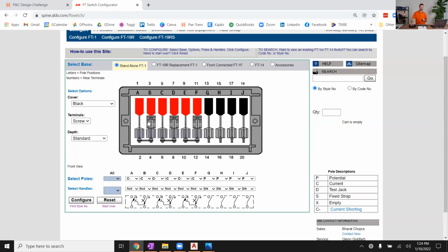If you open the A, or you open the B, or you open A and B, it actually short circuits the field side. I should specify that up here, the odd number terminals are typically wired to the back of the relay. The even number terminals on the bottom are typically wired to the field equipment, to the actual PTs and CTs, and your bushing CTs, your bus PTs, et cetera. And so when you open your current shorting test switches, it shorts 2 to 4. You open C and D, it shorts 6 to 8. Actually, it's a make before break. So as soon as you start to open A, it shorts these before it even opens, to avoid there ever being an open circuit condition on your CT secondary.